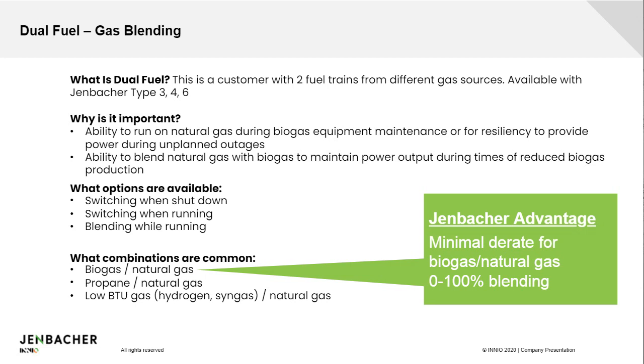So it doesn't have to be off-skid. We basically have, as I mentioned, the two fuel supply trains coming in, and then we handle the mixing and the blending and obviously the controls of doing that. And you can have any number of different set points which determine when and how you switch or blend these gases. The neat thing is that due to our long experience we have in these type of applications, we have been able to basically achieve very good outputs on both fuels. So typically an engine is optimized to one fuel, so you get a better output, better efficiency on one fuel, and the secondary fuel always has a little bit of a disadvantage, but we're very close in terms of output and efficiencies now also on the secondary gas, just through optimizing the engine.